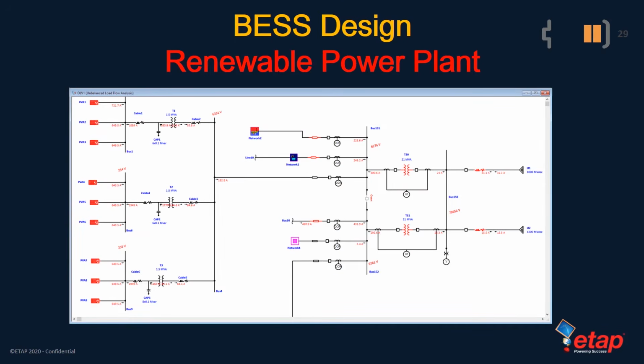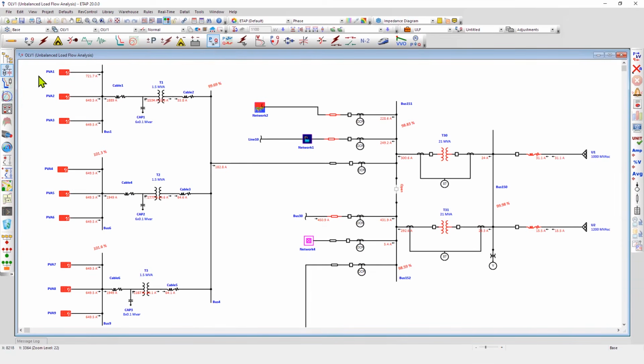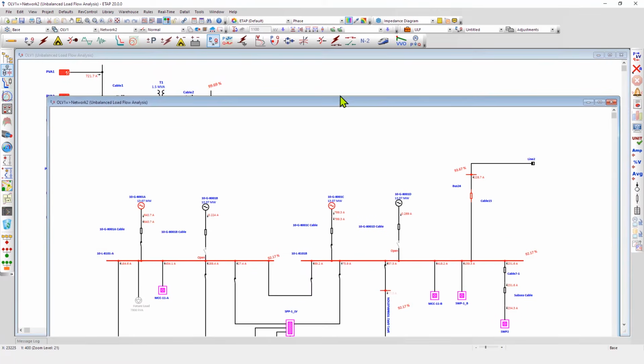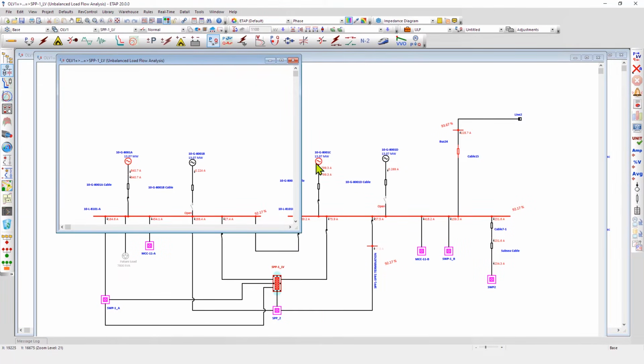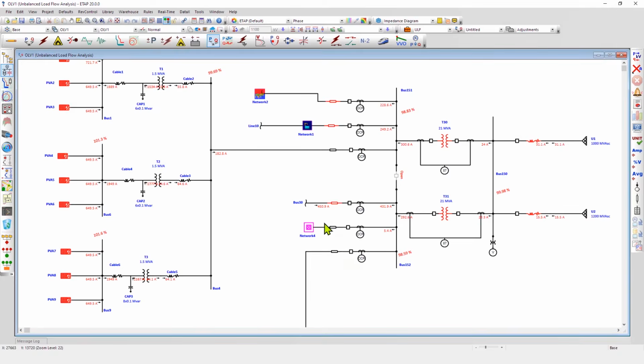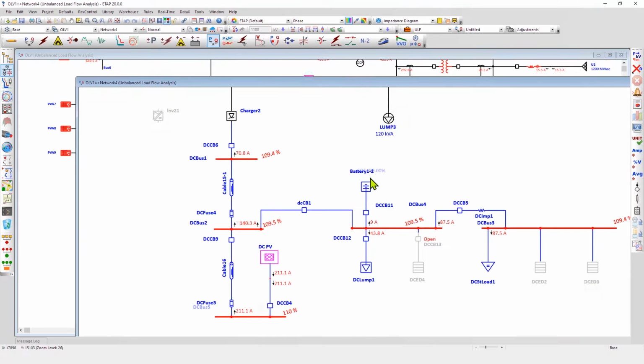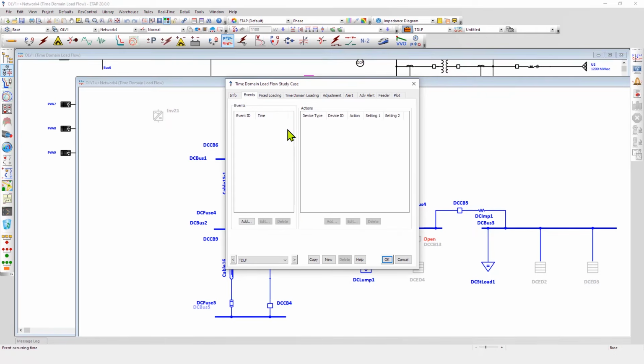Since we've looked at DC systems and unified load flow, the next logical step is to look at time domain load flow. Time domain load flow is particularly useful when we are varying loading or generation as a function of time, and we are including controls such as tap changers, switched capacitor banks, and of course battery management systems as well. Our system includes a number of PV arrays as well as a complex network of generators and loads, and it also includes a combination of a DC network along with the AC system integrated together. Time domain load flow also allows you to define various events.